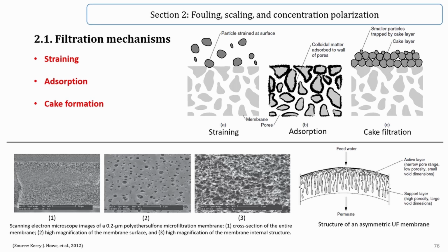Most microfiltration membranes have a homogeneous structure, which means that the structure, porosity, and transport properties are relatively constant throughout their depth. Membrane filters are not constructed of woven or fibrous materials. They are cast as a continuous polymeric structure, as we have already discussed in the previous section, with tortuous interconnecting voids as shown in this figure.